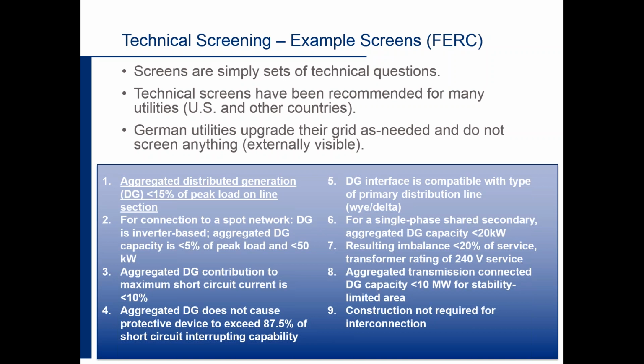And if you pass all of these screens, you can skip impact studies usually. And generally, these screens are passed if you're under 15% penetration on your line. This is typically a very conservative screen. Some utilities are beginning to move away from this metric and look more at planning towards minimum daily load rather than 15% of peak load.